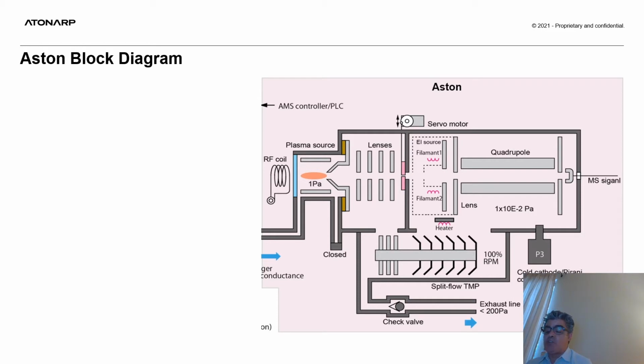Ions then enter the low pressure chamber of the hyperquad, which is outfitted with two filaments. The filaments are either tungsten or yttria-coated iridium, depending on the chemical nature of the ambient gases. The mass filter is driven by a 3.5 megahertz RF supply, covering a mass range between 1 and 300 AMU. Downstream of the mass filter is a dual Faraday cup and secondary electron multiplier detector with a total dynamic range of 9 decades for a low parts per billion limit of detection. Dwell times down to 1 millisecond are achievable for individual species.